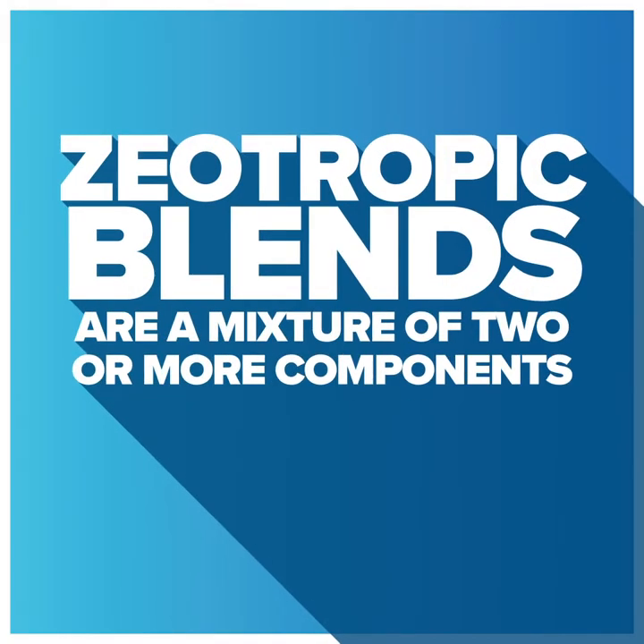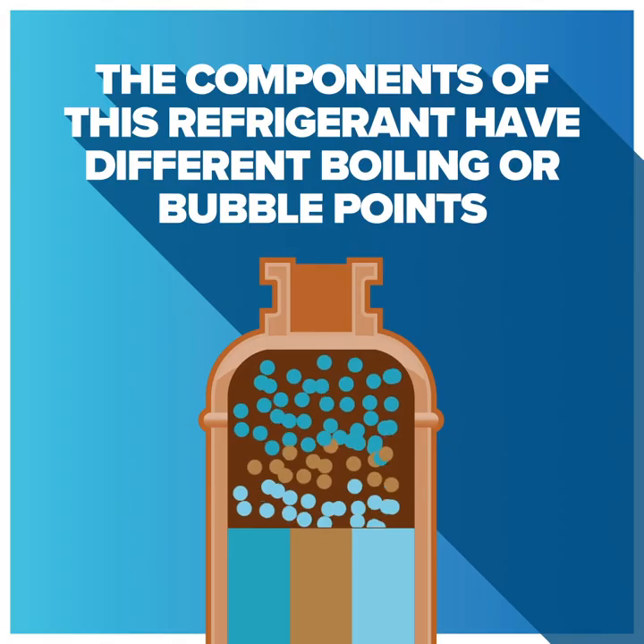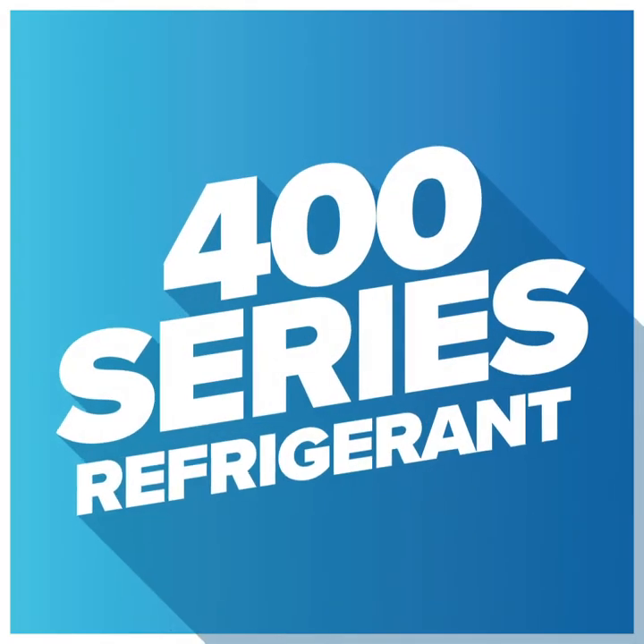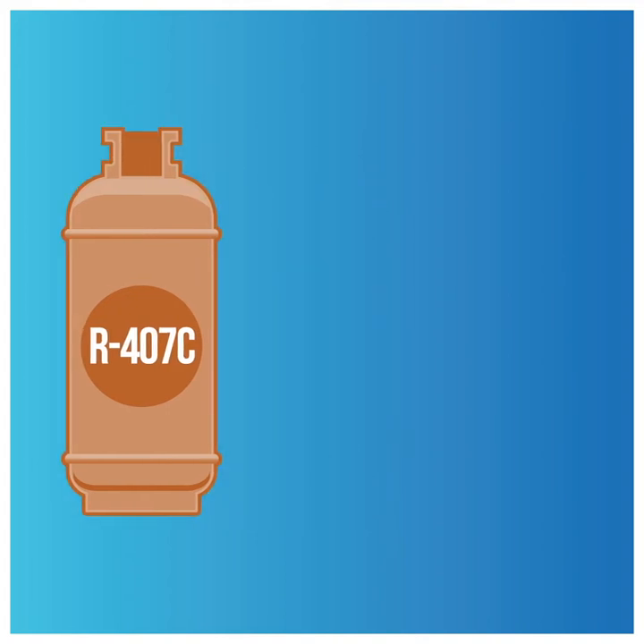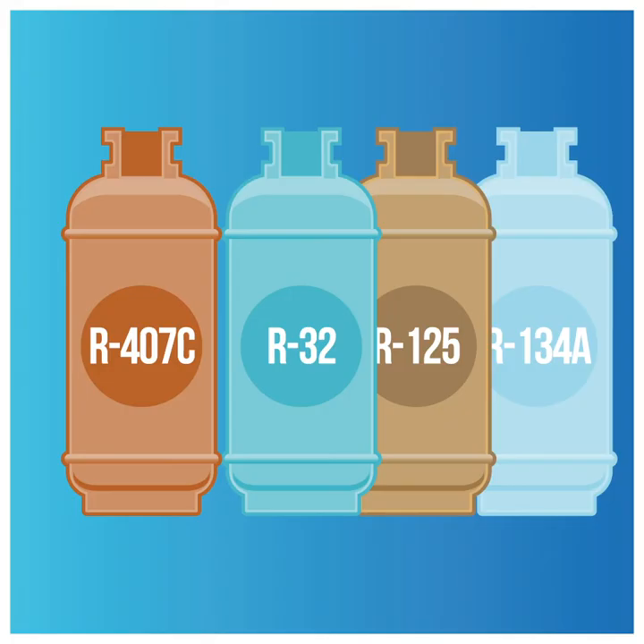Zeotropic blends are a mixture of two or more components. The components of this refrigerant have different boiling or bubble points. An example of a zeotropic blend is any 400 series refrigerant, such as R407C, which is the blend of R32, R125, and R134A.